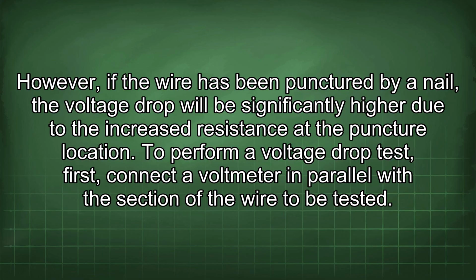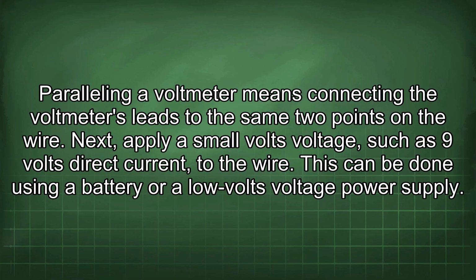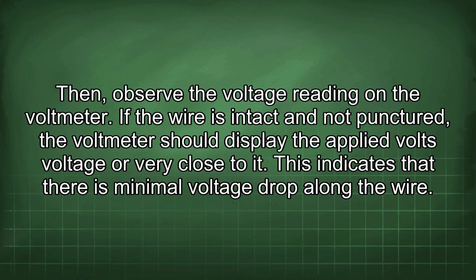To perform a voltage drop test, first, connect a voltmeter in parallel with the section of the wire to be tested. Paralleling a voltmeter means connecting the voltmeter's leads to the same 2 points on the wire. Next, apply a small voltage such as 9 volts direct current to the wire. This can be done using a battery or a low voltage power supply. Then, observe the voltage reading on the voltmeter.